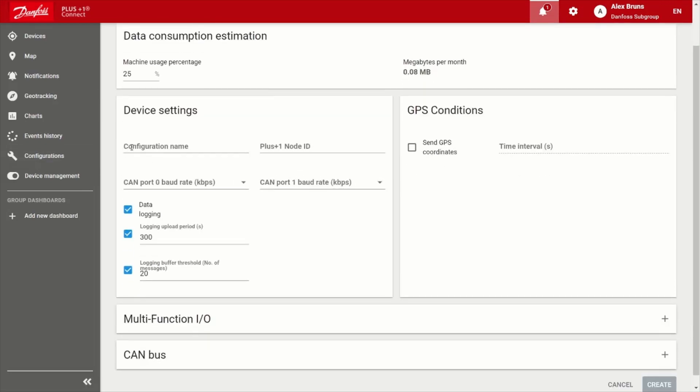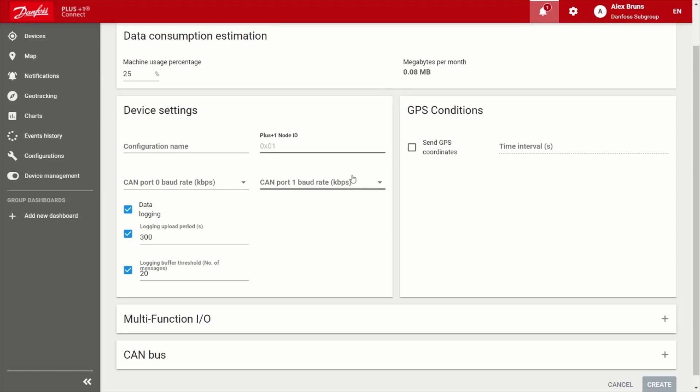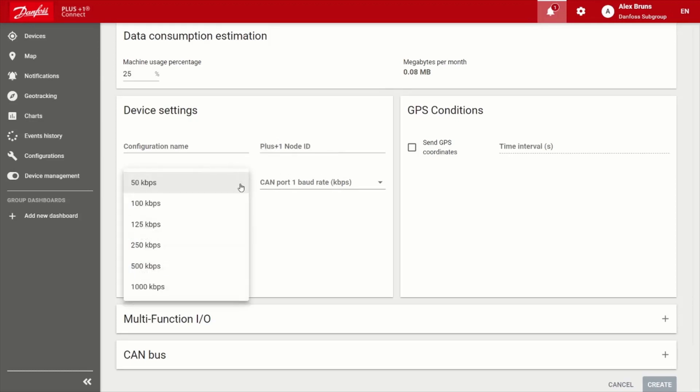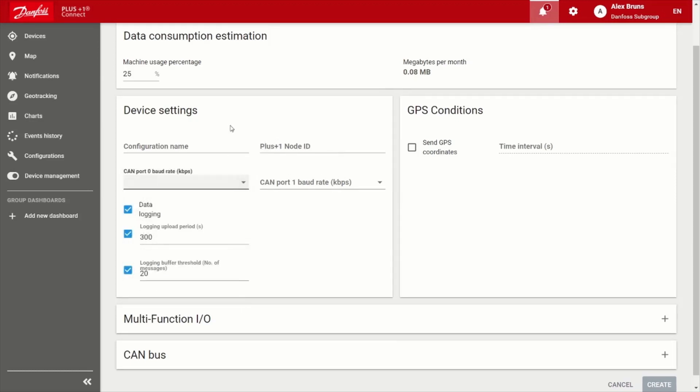So for device settings, of course, you want to give this configuration name so you can keep track of it. You want to choose a node ID that isn't going to cause any issues with any other controllers on the bus. And then there are two CAN bus ports, so you can adjust the baud rates appropriate for your application.